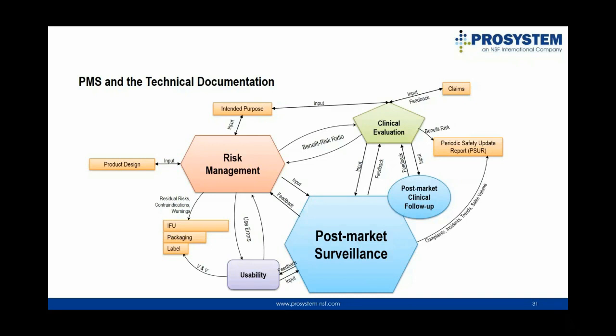The gathered data and the analysis results provide valuable feedback to the interfaces, which are stated in Article 83, Section 3. And among these interfaces, as mentioned, the risk management file and subsequently the product design, the clinical evaluation are the most crucial parts of the technical documentation that are going to require frequent updates triggered by the PMS and PMCF system. This is why you should make sure that the PMS teams comprise experts that are familiar with these interfaces.